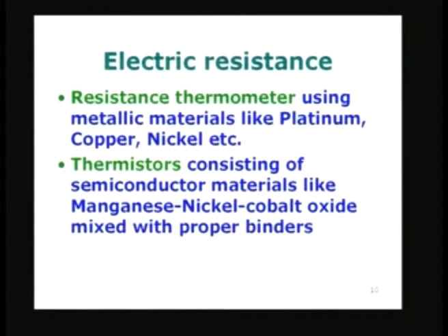Actually the resistance increases with temperature, and this increase is characterized by a regular relationship, and that relationship becomes itself the basic interpolating formula for the platinum resistance thermometer. In principle we can also use copper, nickel and other materials, as long as we standardize them and characterize the relationship between resistance and temperature unequivocally.